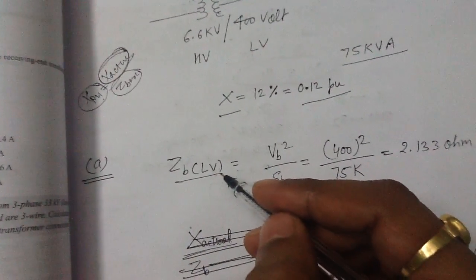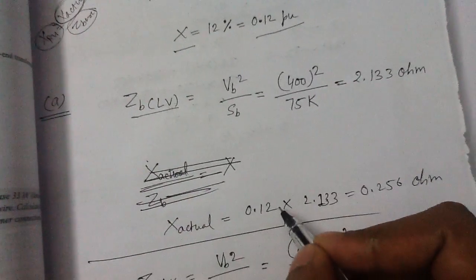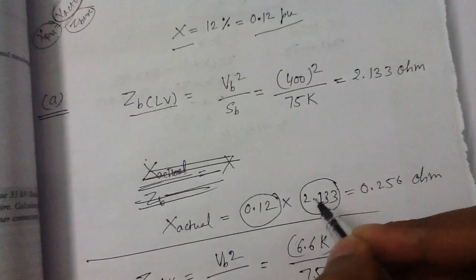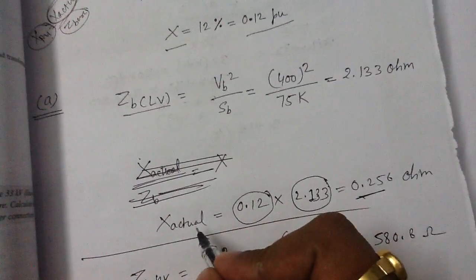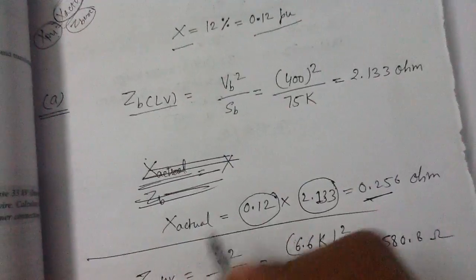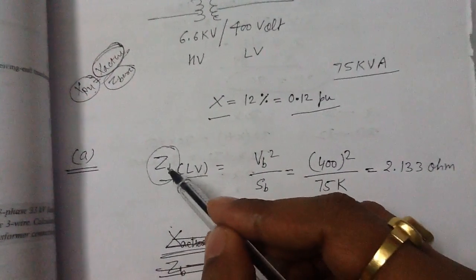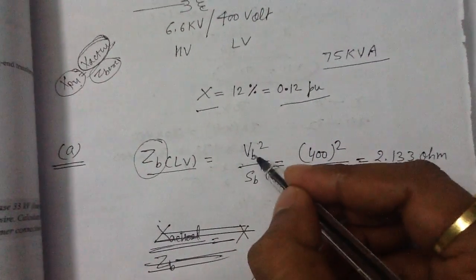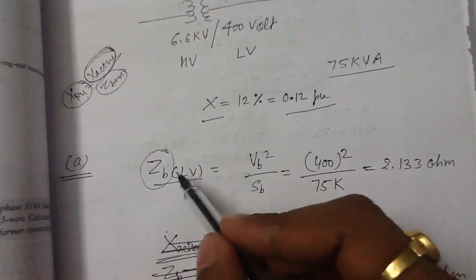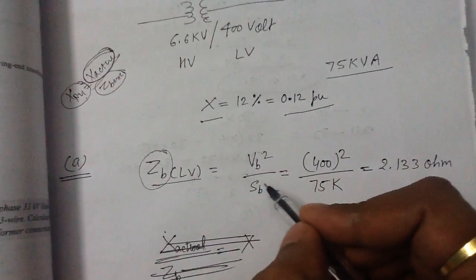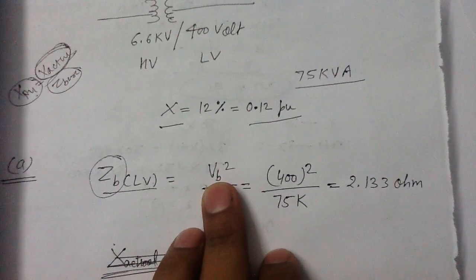If we know the base impedance of the LV side, by multiplying the per-unit value with the base impedance of the LV side, we can get the reactance of the transformer referred to the LV side. The formula for base impedance is base voltage squared divided by S_base.